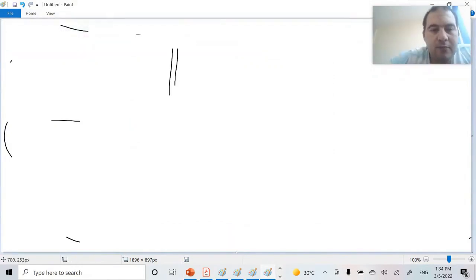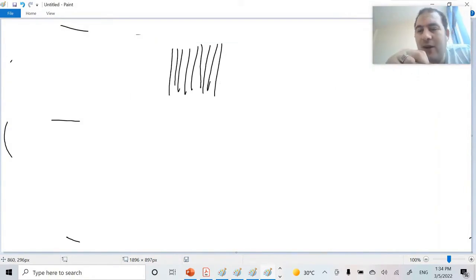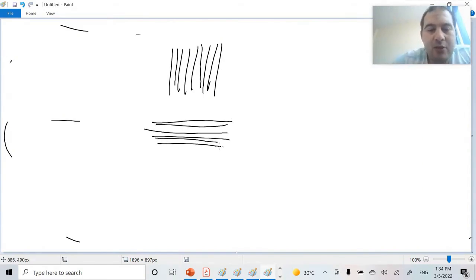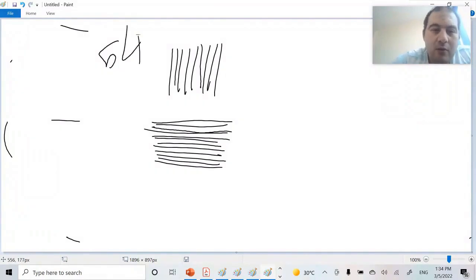For example, a phantom is like a square object, and this phantom contains groups of line pairs. For instance, I might say there are 5 line pairs per centimeter, and then create another group that reduces the spaces between the line pairs, thereby increasing the number.